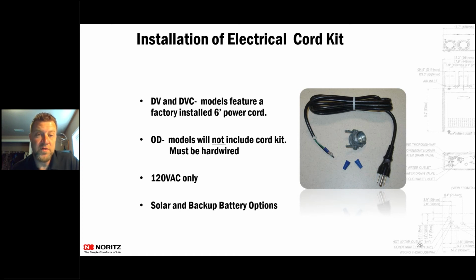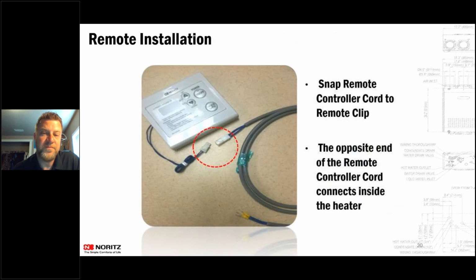So you can run them off solar as well. We've got a lot of units that are put in cabins that don't have electrical going through there. They all run off solar. But the only thing with solar is it needs to be clean sine wave solar for that unit to work properly. Also, if you're running it off a generator or anything like that, we always ask that it's an inverter generator, so it's not peaking and going up and down, but keeping a constant electrical current going to that unit.